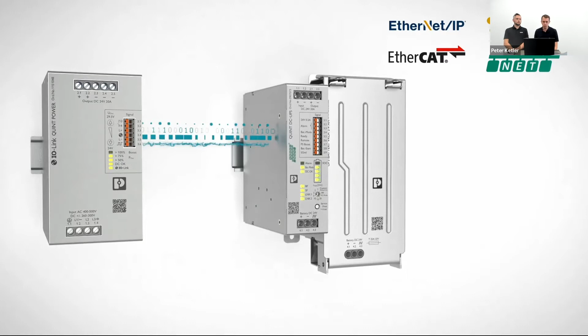The same topic also runs with the UPS, so the power supply communicates to the UPS as well. The difference here is the UPS currently has a wider portfolio of field buses which you can use: Ethernet IP, Modbus, EtherCAT, or Profinet. So the UPS is a gateway for the data, to get the data out of the power supply and the DC UPS.